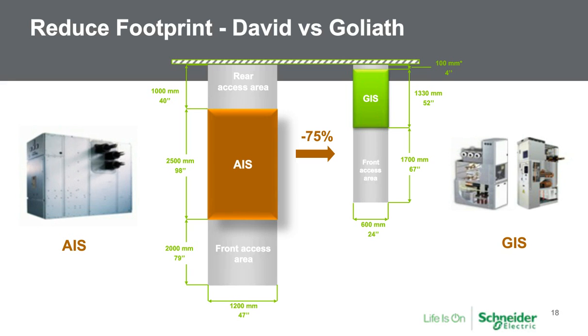On top of that, we get into compactness. If you compare just the real estate that a GIS section takes up compared to an air-insulated metal-clad piece of switchgear, now here we're focusing at 38 kV, you can just see that it's vastly, vastly more compact. In addition, most GIS manufacturers do not require rear access. So when you're trying to shrink down an e-house or really optimize your layout in a building, you don't need rear access. Cables or terminations are typically accessible from the front or from the bottom through a gallery. That means you can again save on space and save on money there.